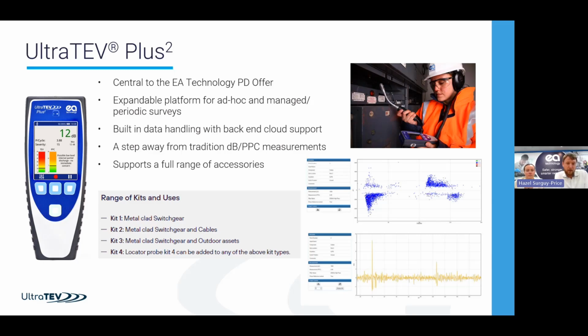It'll do a lot of analysis automatically on the device. It will tell you, for instance with ultrasonics, that yes, this is PD, this is noise. It'll also record lots of information in the background that allows experts and more central office support to back up your decisions rather than having to make every decision on site. It is applicable to everything from cables, metal clad switchgear, outdoor compounds, GIS installations. There are accessories across our full range now, covering UHF and wider. So quite a flexible device in that sense. So that's the technique we choose to move forward with.